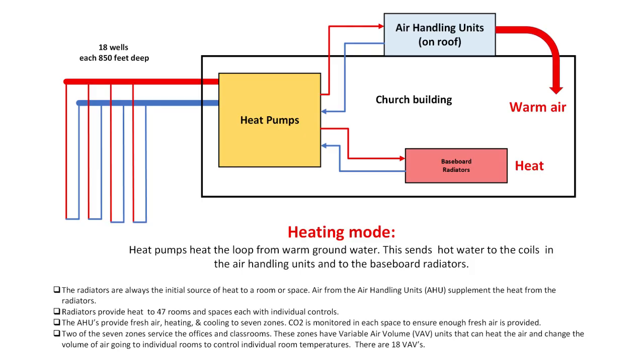But heating all the air to one temperature in a zone, like you would do in your house, like your first floor zone heats all the rooms in your house on the first floor to a certain temperature, that works fine at home, but doesn't work in a building where you've got 47 different classrooms and different occupancy, some manned all the time, some at night. So we have to adjust the temperature within a zone. That's done by variable air volume units. They take the air that's coming down from the roof at a certain temperature, and they can both heat it up if we have to warm it up to make that room warmer, or reduce or change the air volume going to that room if we have to lower the temperature. So that's how these 18 different variable air volume units we have control the temperature to individual rooms, primarily the offices and classrooms on the first and second floor.